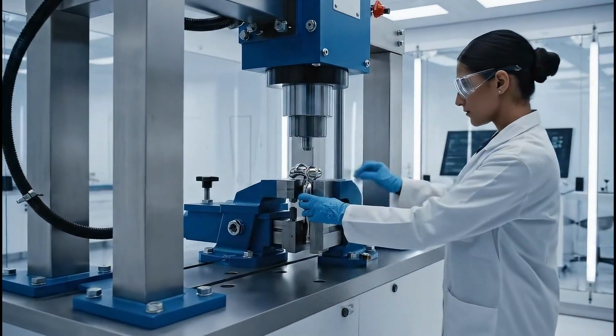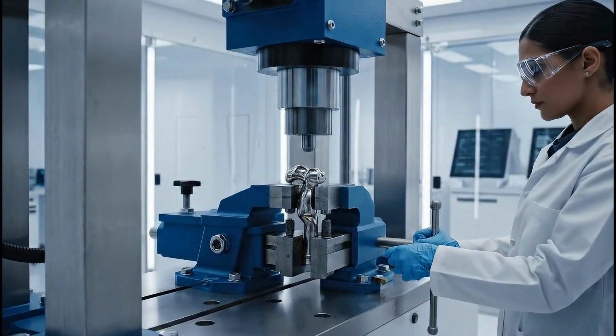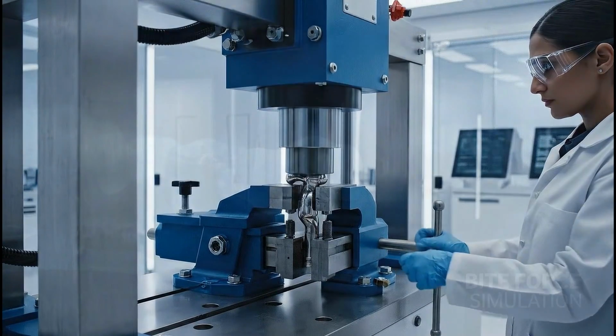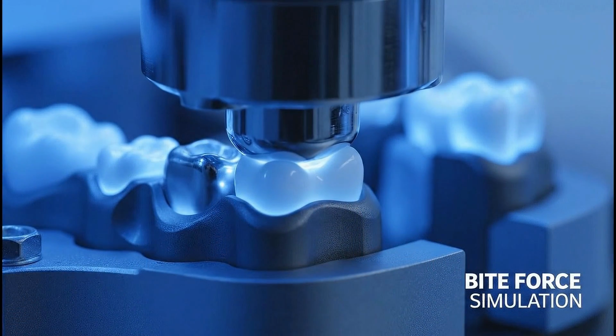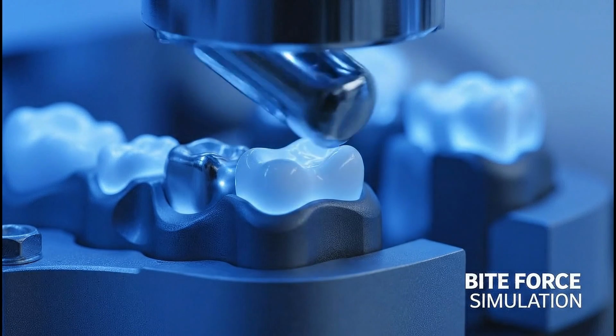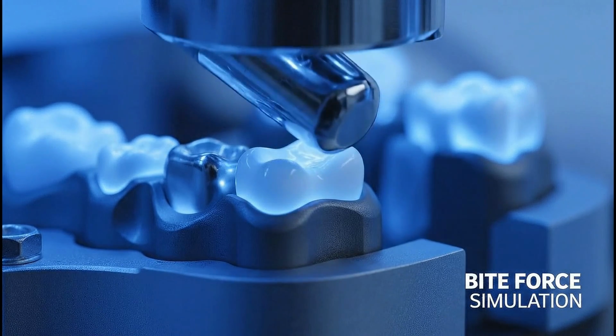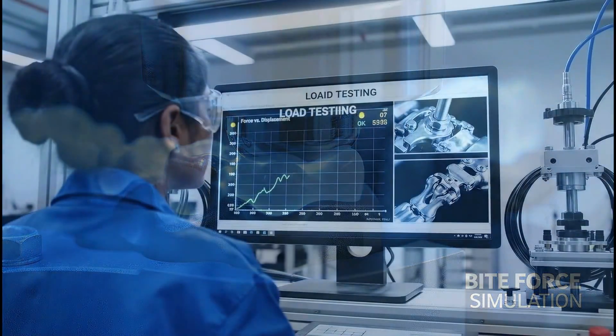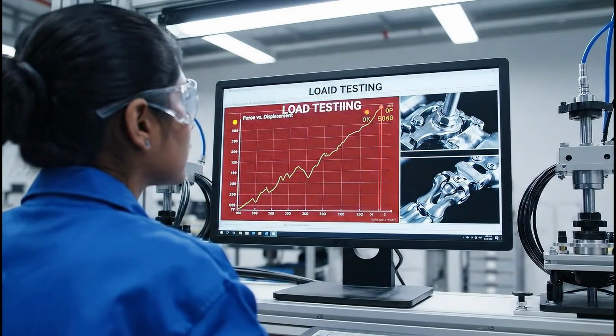We select random samples from every lot for destructive testing. These parts will never be sold. They are sacrificed for safety. This machine simulates the force of a human bite. It applies off-axis load to test the implant's stability. We push the implant well beyond normal physiological limits. The graph shows the metal flexing, but not breaking.